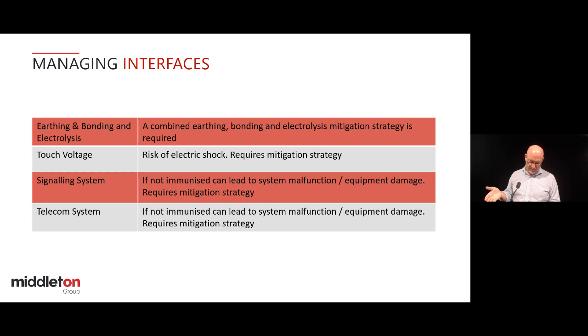So at the interface, you need to put forward a combined earthing and bonding strategy that works for both. And that means you're managing the touch voltages that come with the general operation of the railway. Touch is where people can actually touch assets at different potential, and also under fault conditions. It also means you need to allow for different return paths for fault currents. So you want the DC fault current to go back to its source, and you want the AC system to go back to its source, preferably not to get confused and try and go back through each other's return circuits. Usually some compromise is required. So that's one of the things to worry about.